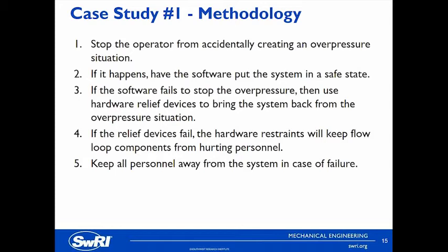For this facility, our methodology is: first, stop the operator from accidentally creating an overpressure situation, and if it happens, have the software put the system in a safe state. If the software fails to stop the overpressure, use hardware relief devices to bring the system back from the overpressure situation quickly. If the relief devices fail, hardware restraints will keep flow components from becoming projectiles and hurting personnel. And finally, keep all personnel away from the system in case of failure.